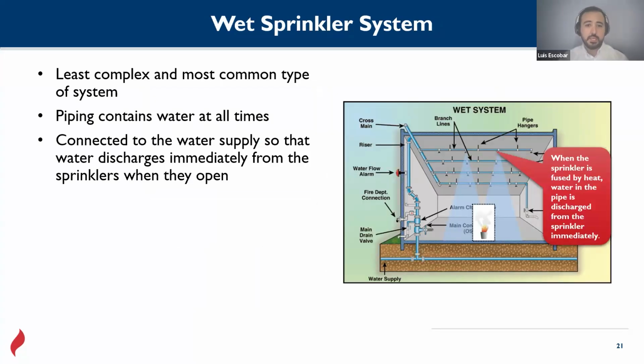Wet sprinkler systems. The way to differentiate this one from the other ones is that there's always going to be water inside all pipes. These pipes you see here, here, and all over the place contain water inside them. That's why it's called wet. All systems, when there's a fire, release water. Let me get that clear. But the difference for the wet system is we always have water in the pipes. It's the least complex and most common type of system. As I was saying, it's probably 80% of the systems that we design, and most of them for indoor occupancies. Connected to the water supply so that the water discharges immediately from the sprinklers when they open.